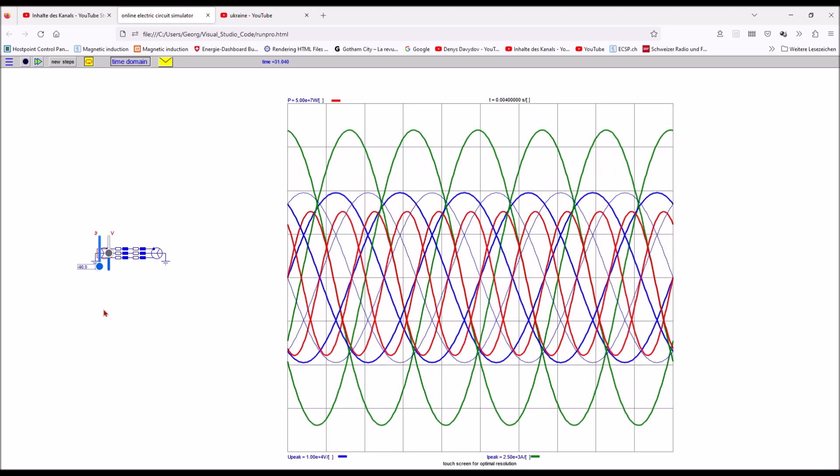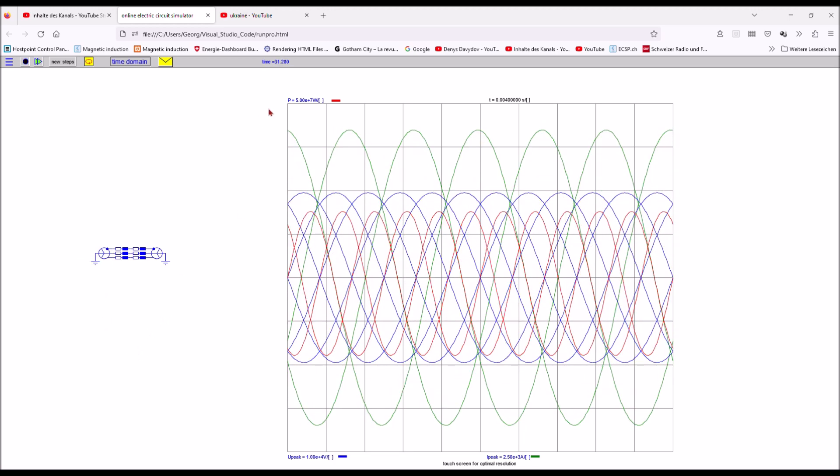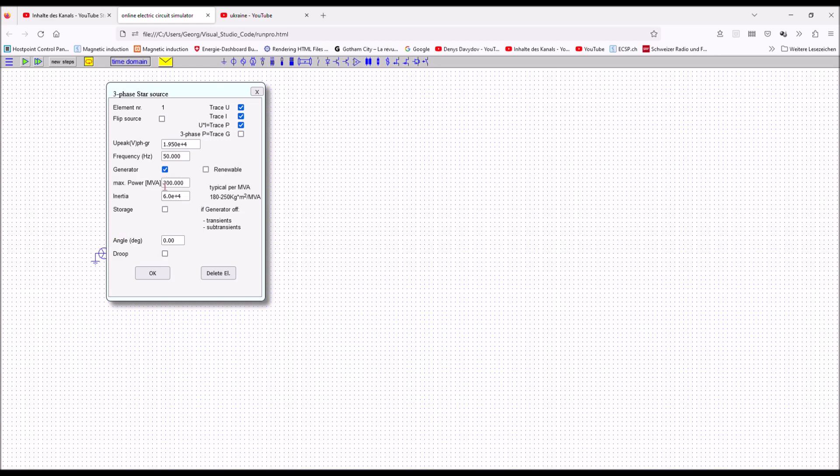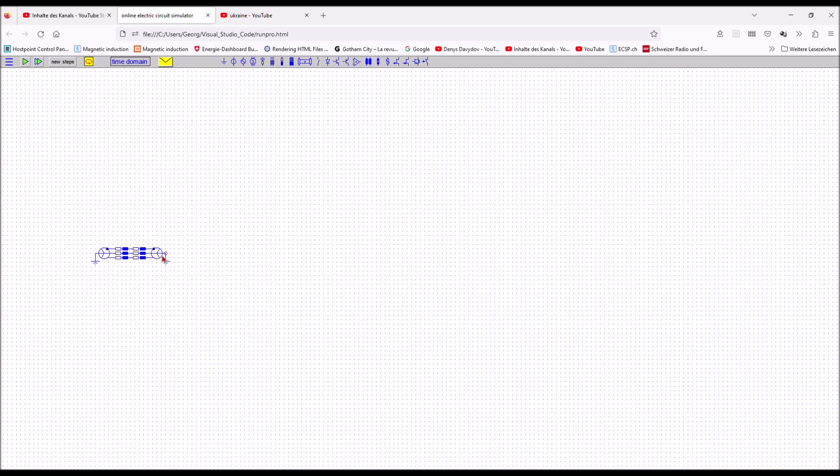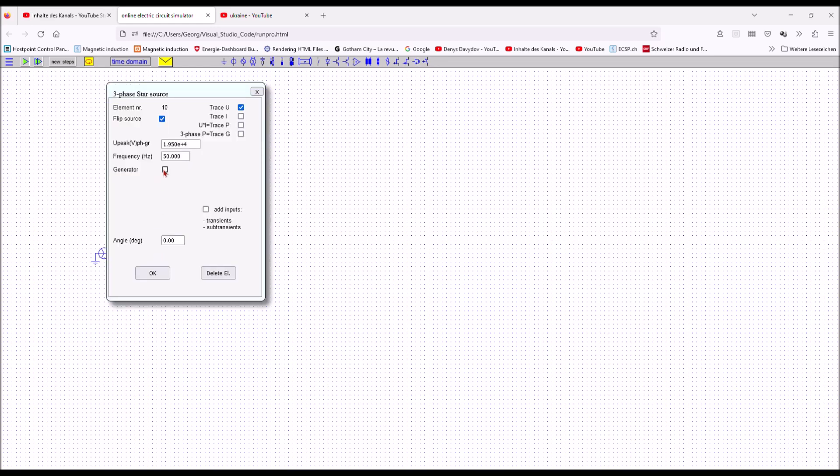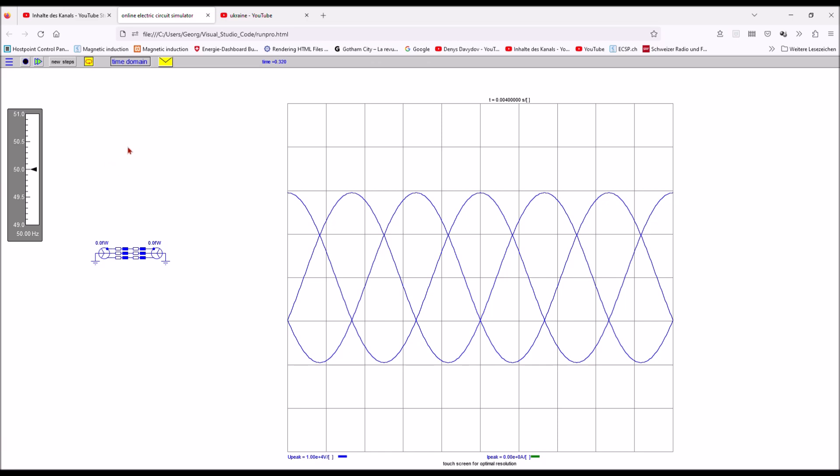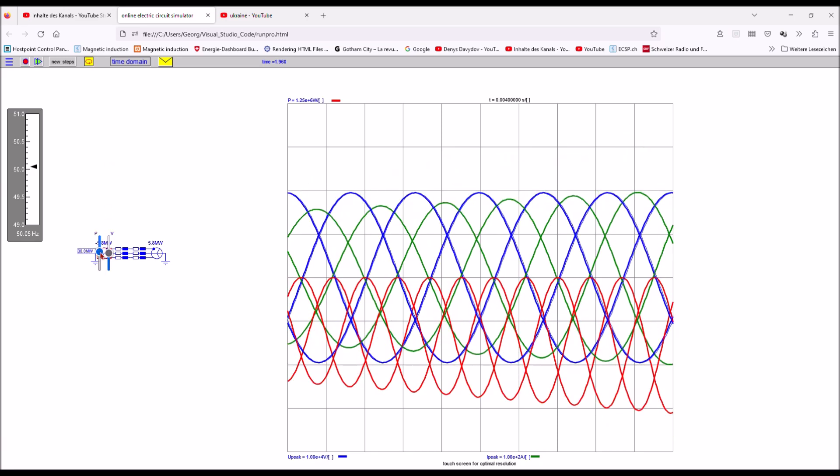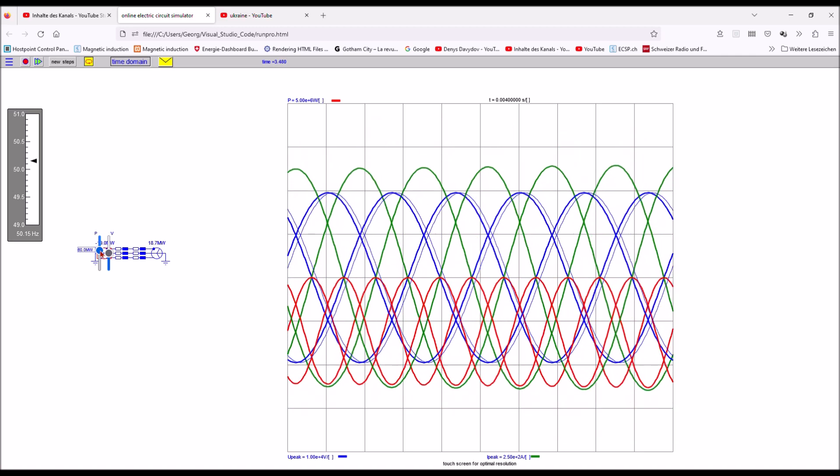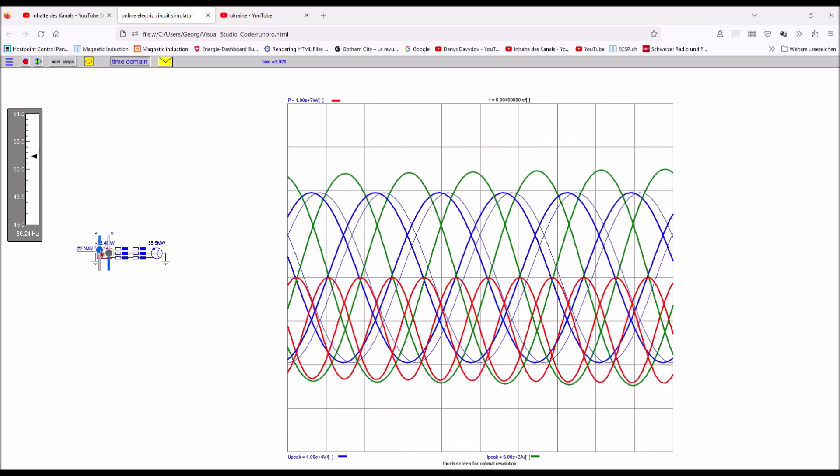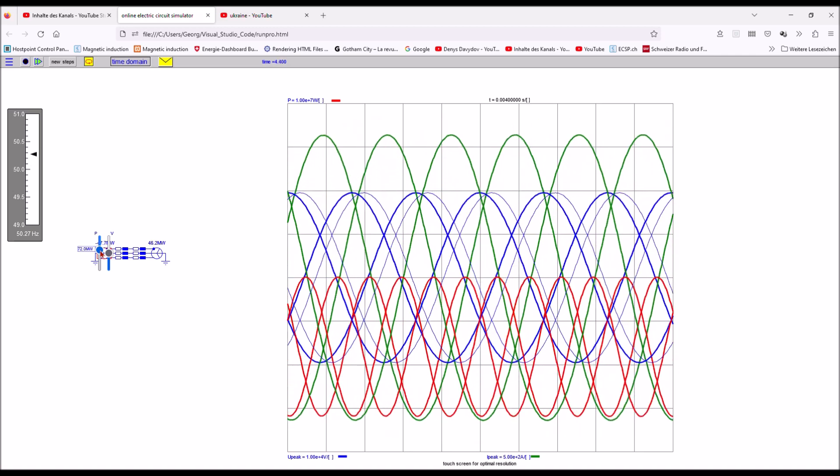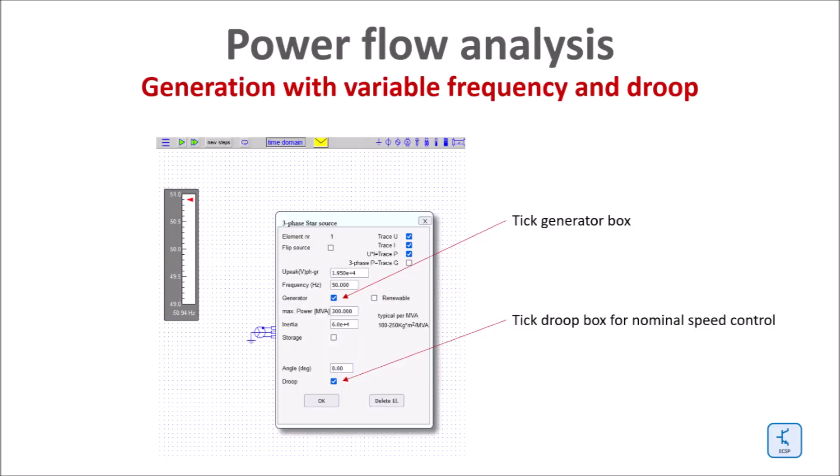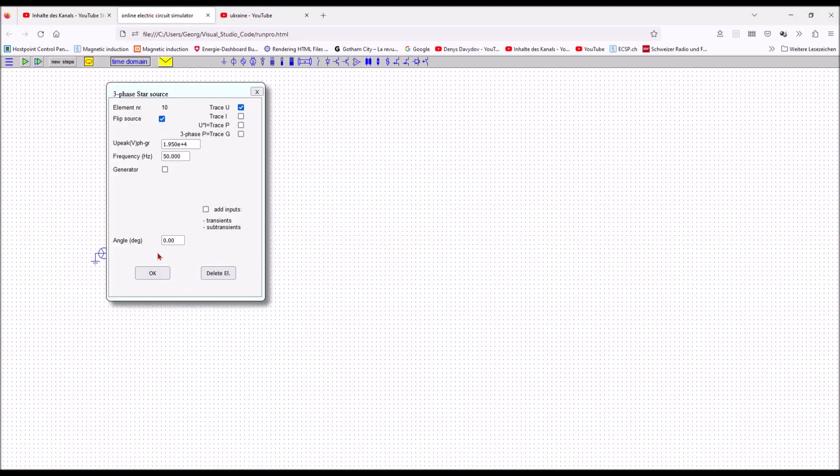So far we have been working with voltage sources and rotor angles only. There is still one trick missing: the mechanical torque and the resulting acceleration of the rotation frequency. The frequency is a key parameter for the stability of a power grid. A surplus in power generation accelerates the rotation frequency of all connected synchronous generators and vice versa. If the frequency exceeds 50 or 60 hertz the torque on generators is automatically reduced or increased in case of under frequency.